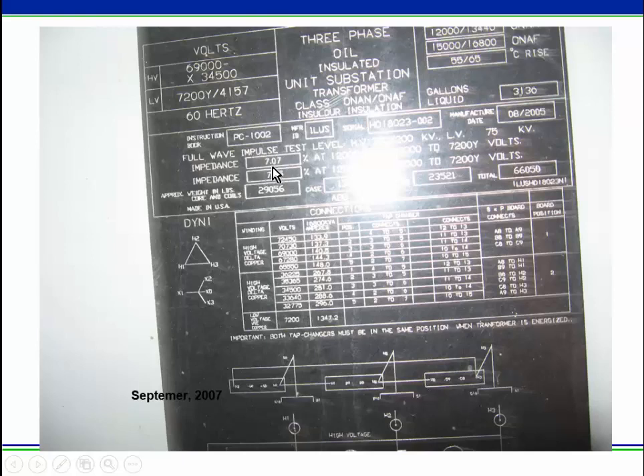Notice here the impedance of this guy, 7%. Sometimes that'll be Z. The BIL you can't see very well, but this says full wave impulse test, which is the same thing as BIL. It says the low voltage was tested at 75 kV, which should be good. So that's just an impulse for a little bit. Notice this is a 7,000 volt transformer, 75,000 volt impulse test. And then these here are different tap arrangements, again, to move the voltage. These are what we call no load taps. In other words, we change it de-energized.